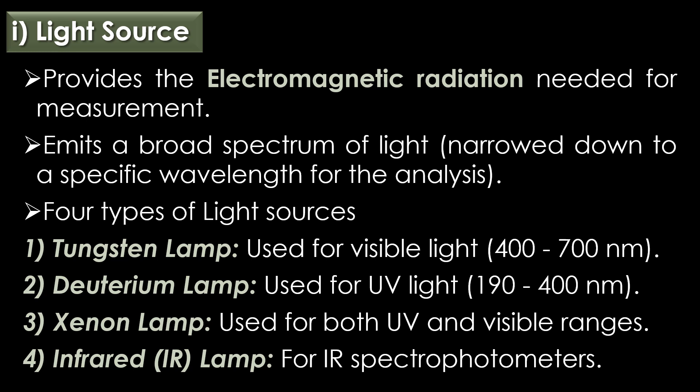Light source: the light source provides the electromagnetic radiation needed for measurement. It emits a broad spectrum of light which is narrowed down to a specific wavelength for analysis. Four types of light sources are available: tungsten lamp, deuterium lamp, xenon lamp, and infrared lamp. The deuterium lamp is used for ultraviolet light from 190 to 400 nanometers, the xenon lamp is used for both UV and visible ranges, and the infrared lamp is used for infrared spectrophotometers.